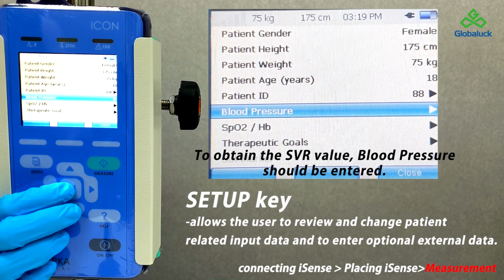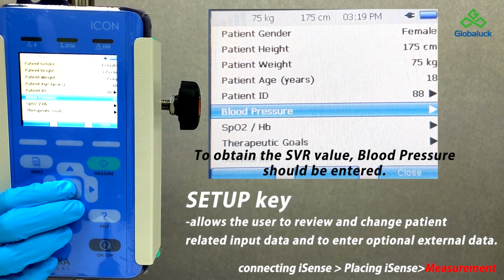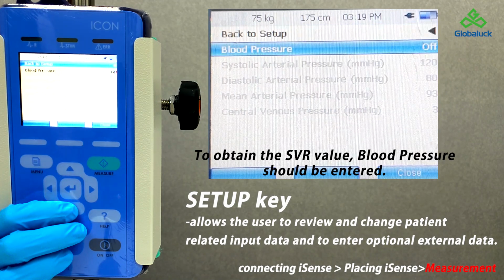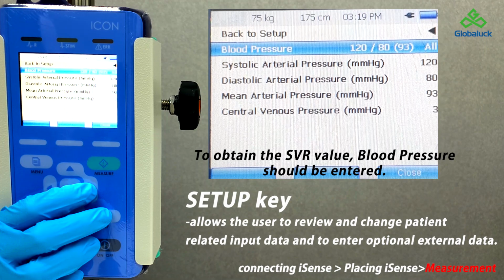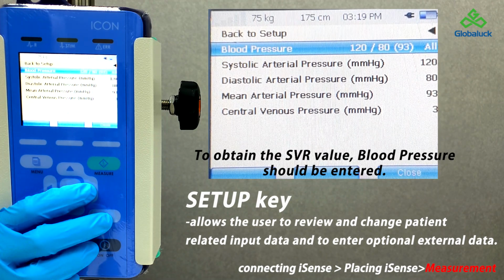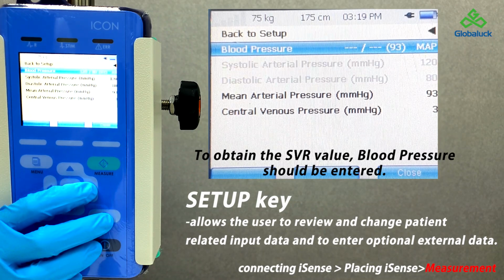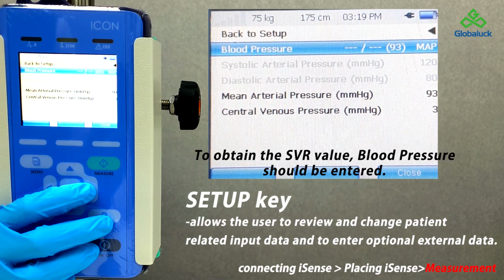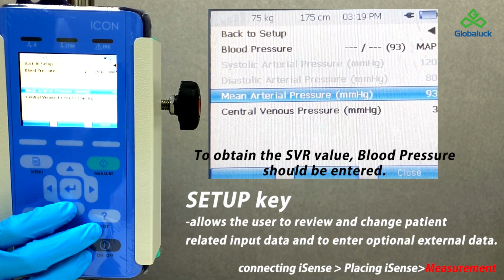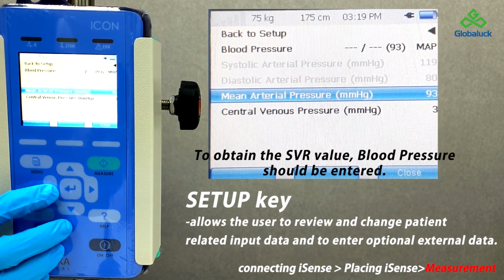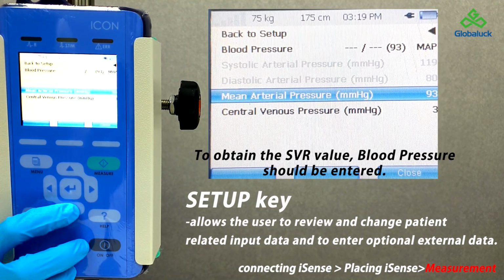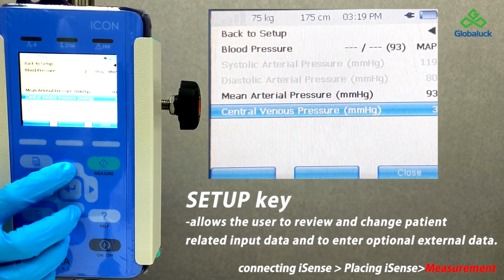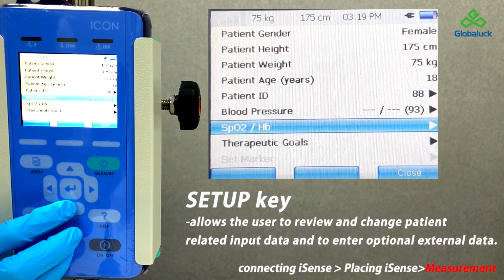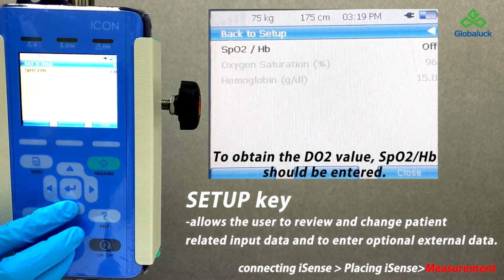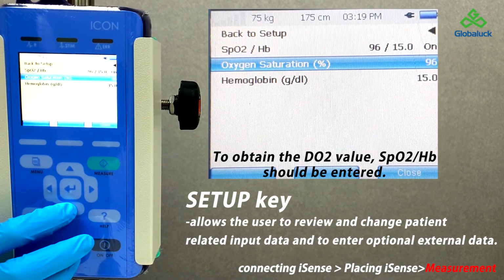To obtain the SVR value, blood pressure should be entered manually if it is activated from off to on. You could input the blood pressure as the value of the mean arterial pressure. The alarm will go off every 30 minutes to change the blood pressure values if the blood pressure is activated. To change the blood pressure value, press the Setup key even during the measurement. Press the Enter key if you do not want to change the blood pressure value, then the alert window will disappear. The default value for CVP is 3 mm Hg, and you can change the value. To obtain the DO2 value, you should input the oxygen saturation and hemoglobin of the patient.